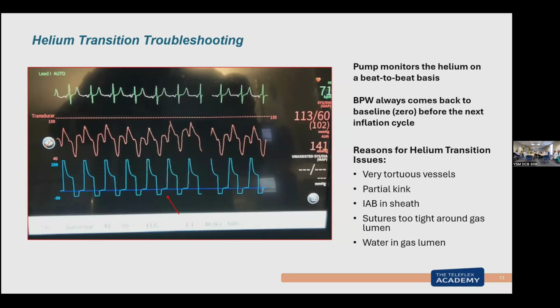If you see moisture in the tubing and we open the little door and there's only half a jar full of water, I would empty it. Then the other thing: if the tubing is dangling down below the insertion, get the tubing up so it's easier for the pump to evacuate that tubing. I had a staff person call me one time and they had water sloshing back and forth with the balloon inflating. Once we elevated the tubing, the pump cleared it out. So you don't want it dangling down, because that makes it harder for the pump to get rid of that condensation. Condensation is normal because we've got cold helium going into a warm body, which creates condensation.